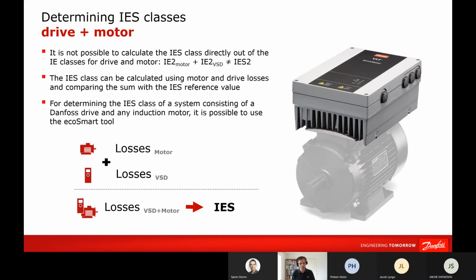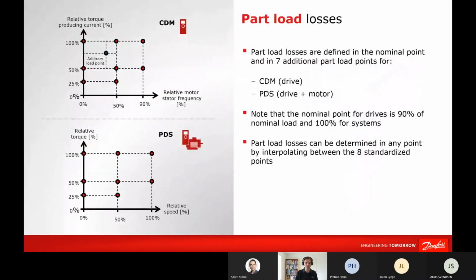It is needed to look at the losses in the motor, the losses in the drive, add them, and then compare the result with a reference value from the standard, and that will then determine the system efficiency class. Part load losses are especially important because part load losses are what's needed for determining the energy efficiency index.